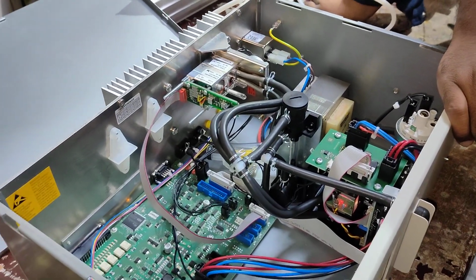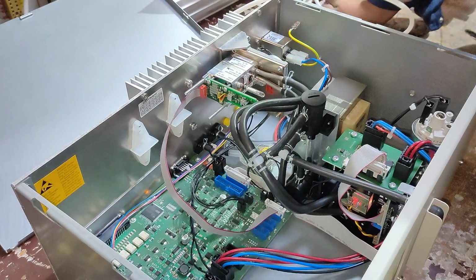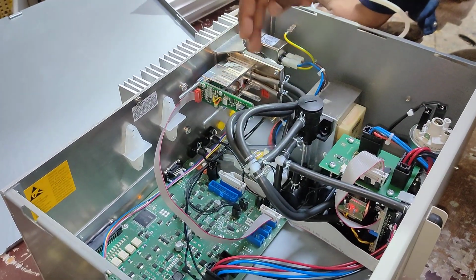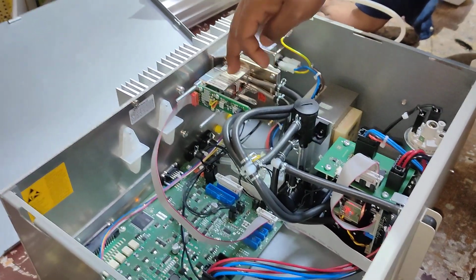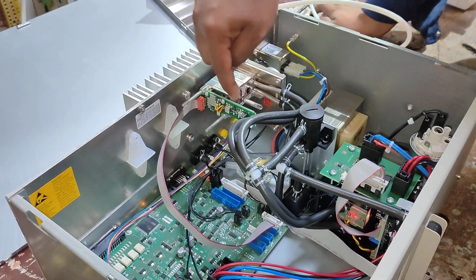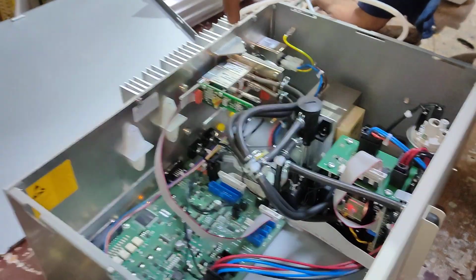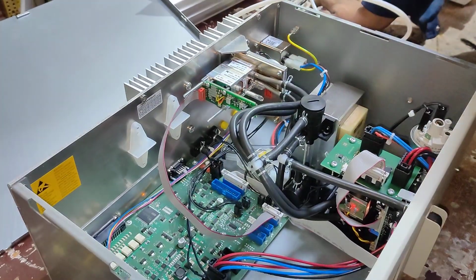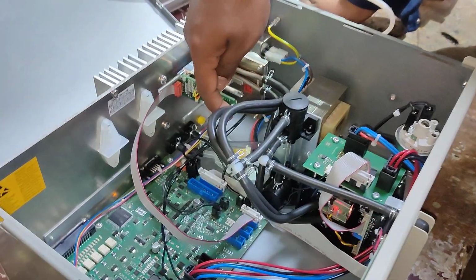Last time, you were adjusting from the back side for that. In this one, it is not required. The reason is we don't have a reference cell in this. We have only the measuring cell. The reference is in the PCB. The Wheatstone bridge is sitting in the PCB, so they have set one reference. That reference we are setting with the feedback resistor.